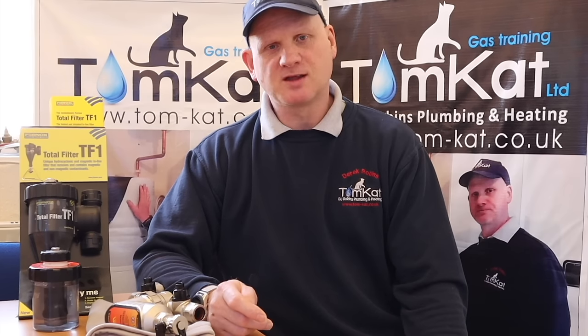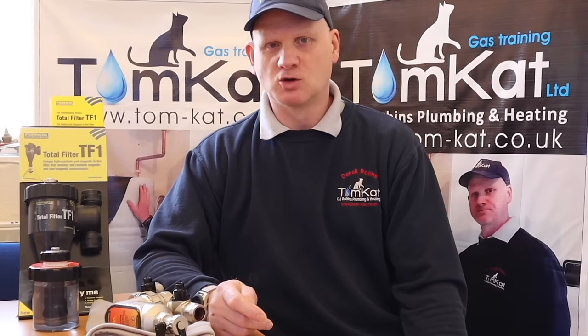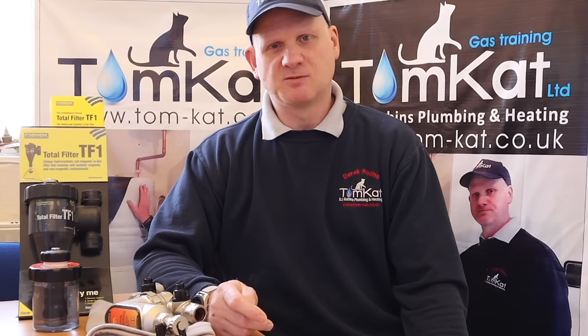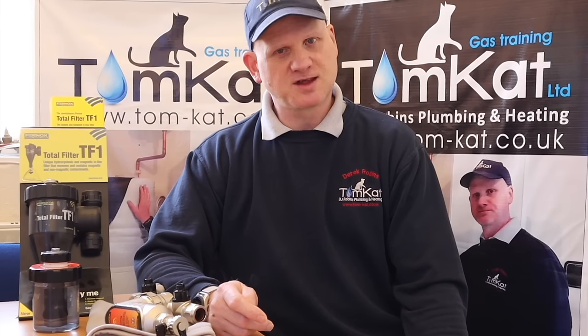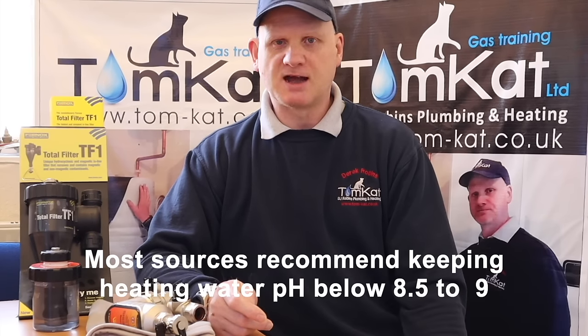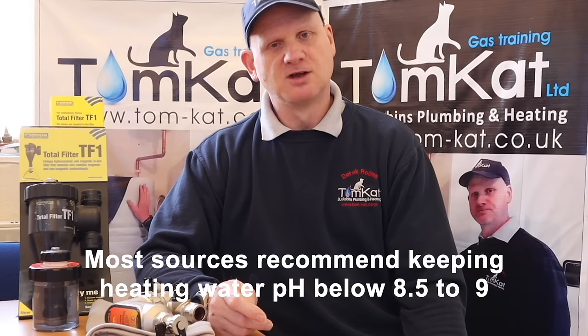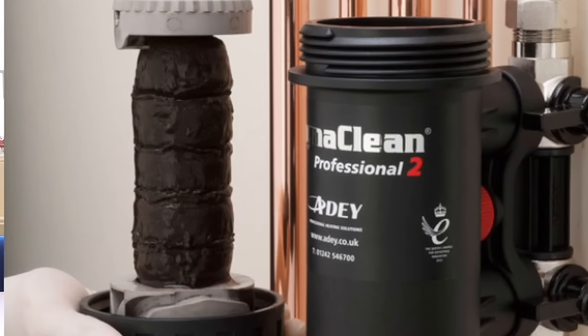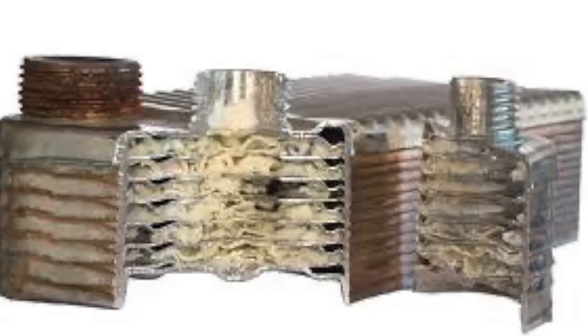But when engineers find boilers in poor condition, they normally say to the customer, "You need a new boiler." This can all be averted by just having the boiler serviced and the system water checked regularly. Now, according to the new Benchmark scheme, when you service a boiler, you must check the water quality for its pH level to see whether any inhibitor needs to be added, and then every 5 years it'll need to be redosed. We frequently hear about sludge in our radiators and in our central heating systems. Sludge refers to the corroded metal in our system, which is commonly known as magnetite. This magnetite eventually blocks radiators and blocks plate-to-plate heat exchangers in the boiler, which makes the boilers very inefficient and damages the system.